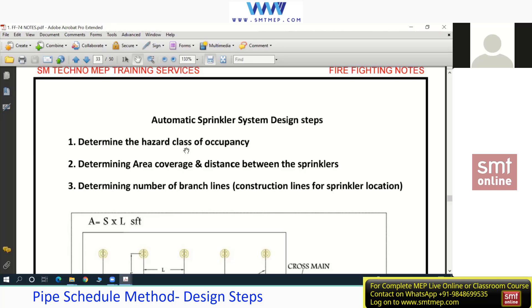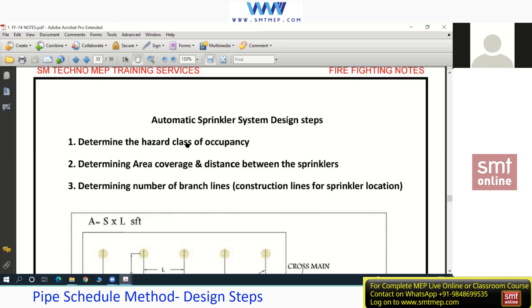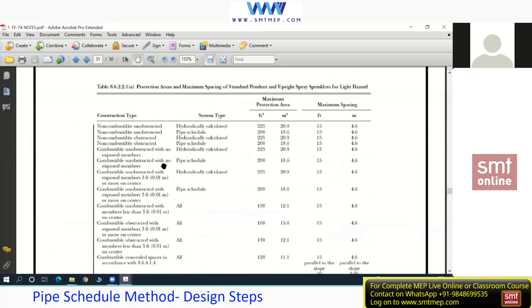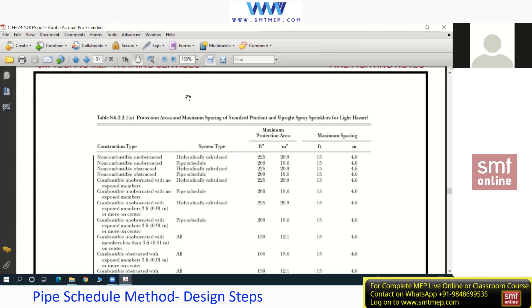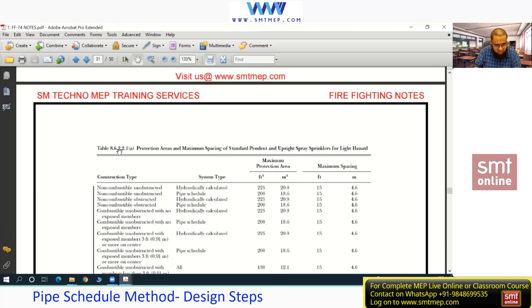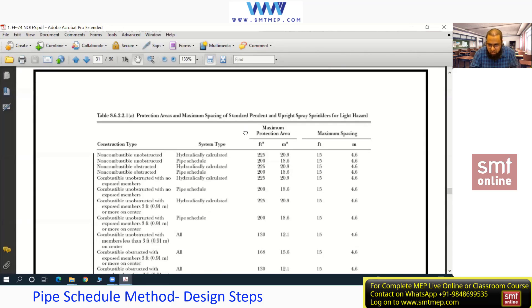Once you get the hazard class of occupancy — light, ordinary, or whatever it may be — Step 2 is to determine the area coverage and distance between sprinklers using the tables. The table referenced in the notes is Table 8.6.2.2.1 from the 2013 edition. We are now using the 2019 edition, so note the updated table number from your NFPA folder. On page 31 of your hard copy, you can write the updated table number above the old one.